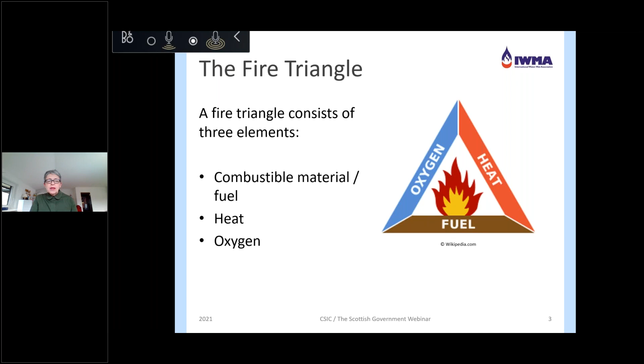I suppose that all of you know that the fire triangle consists of 3 elements: the combustible material or fuel, the heat, and the oxygen. And the thing is that water mist reduces 2 of these elements, the heat and the oxygen. Another thing is that water mist is a performance-based technology, which means that you will always get a bespoke system for your application, which is based on a real scale fire test, not on computer simulation, because water mist is not a one-fits-all concept.